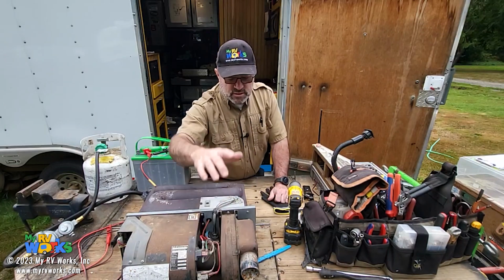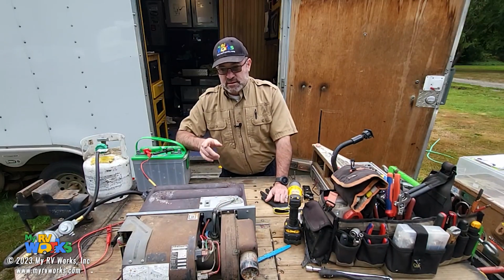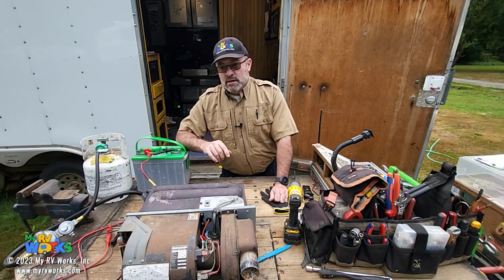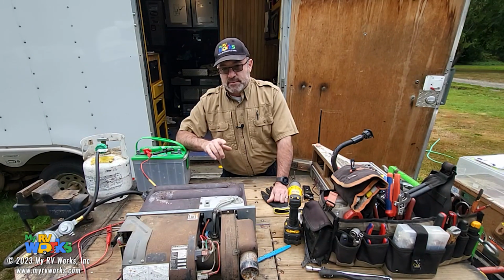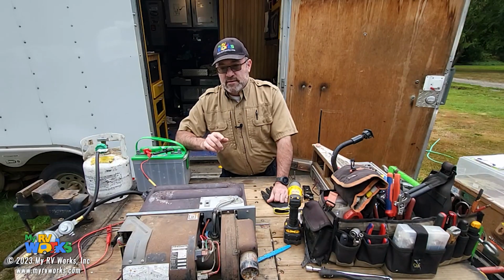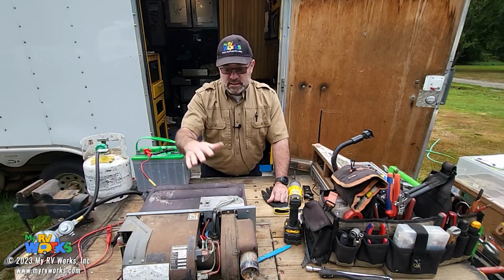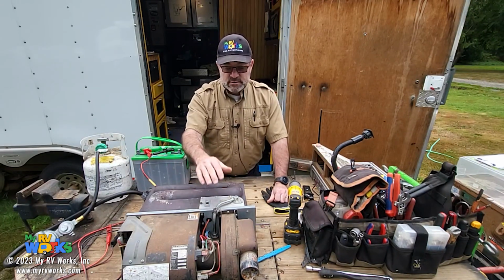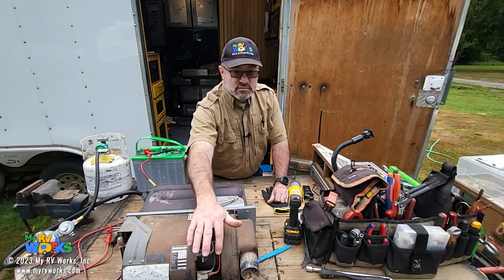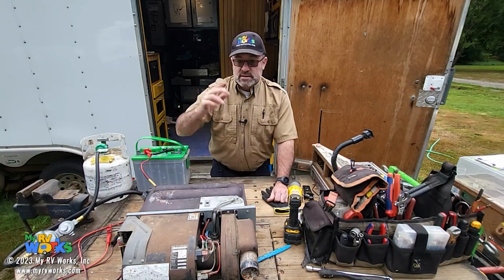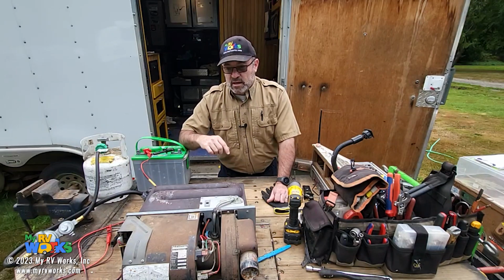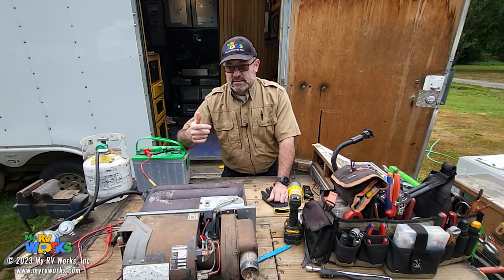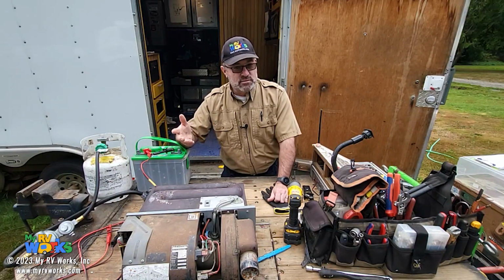When the sail switch trips, though, we don't see that as often as extinguishing and igniting, extinguishing and igniting. Because when the sail switch trips, the control board needs to see the furnace stop and start again, okay? So if your issue is with your sail switch, it's not likely to be one of these intermittent things where it keeps running but ignites and extinguishes, ignites and extinguishes. So that's likely not a sail switch fault, okay? The way the sail switch works with open and close, the control board needs it's like a latching relay, okay, if you're a controls engineer.